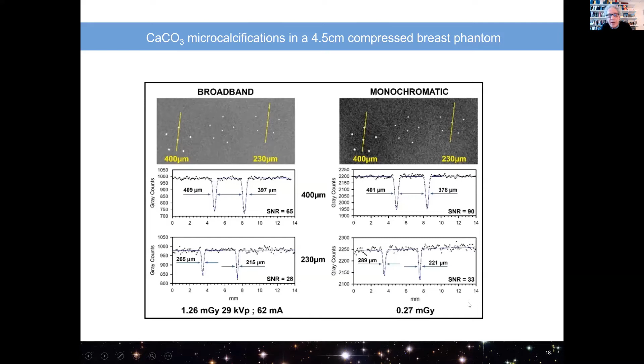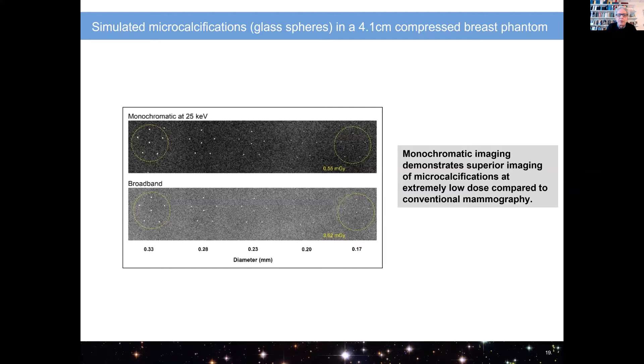This is one of my favorite slides. This shows the imaging of glass spheres, which are a little bit more difficult to see than calcium because the atomic number of the glass is lower than calcium's atomic number. But these range in size from 330 microns all the way down to 170 microns, but the dose for the mono image is 0.55 compared to 3.62 for the broadband source. Similar comparisons for the 9 centimeter thick breast from the broadband to the mono. Again, 2.75 milligray to 0.65.